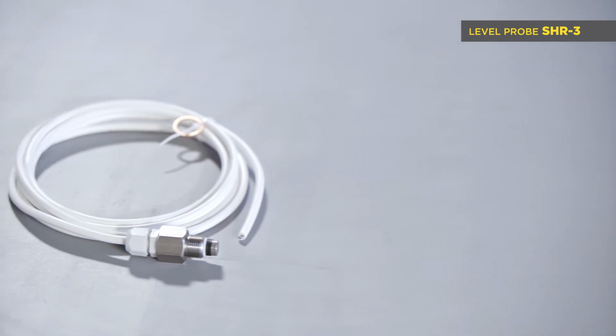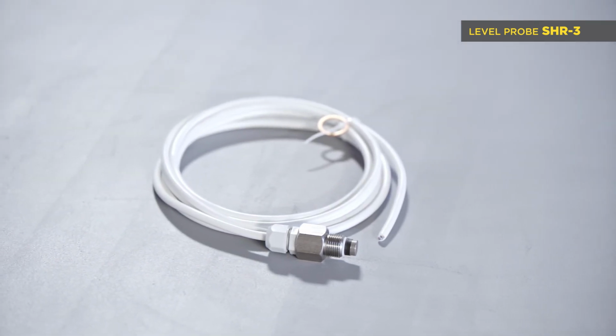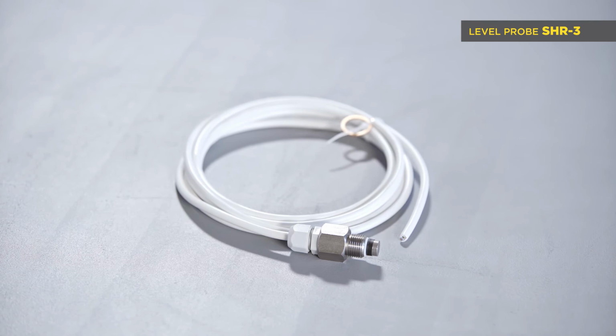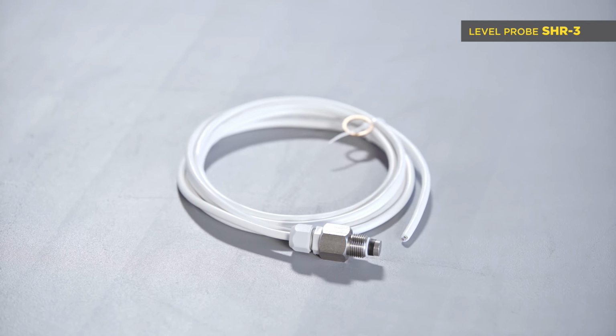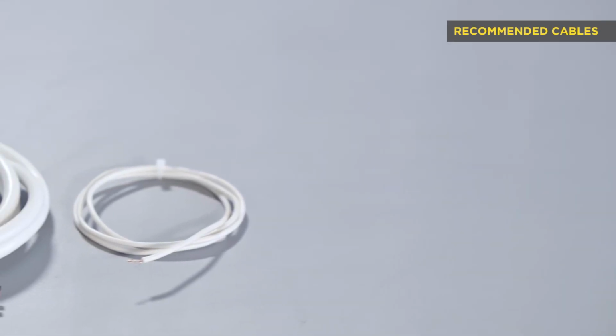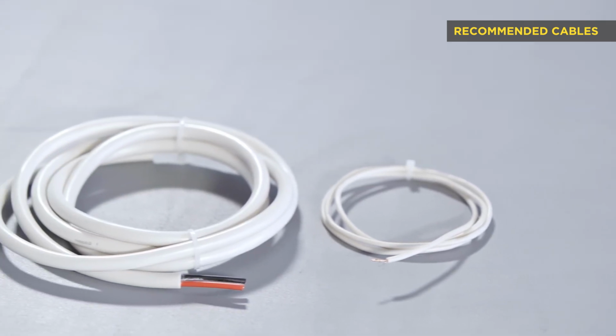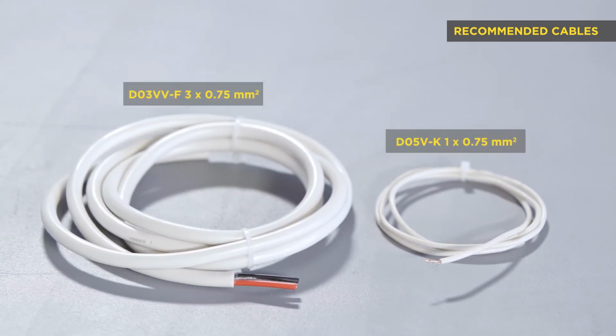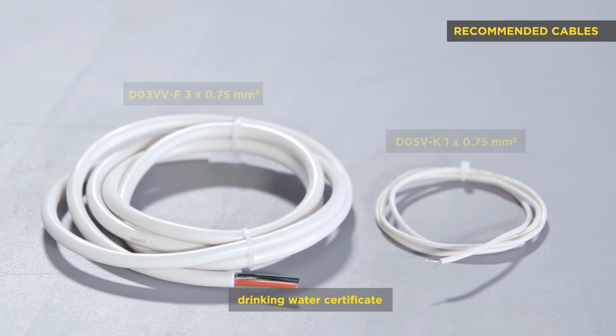SHR3 is an industrial electrode made from stainless steel with screw thread M18 with 3-meter long cable. It is suitable for direct installation into a closed tank with pressure up to 4 megapascal and operating temperature from minus 25 to 60 degrees Celsius. We also offer another accessory, a probe wire with 1 by 0.75 millimeters squared conductor, or a cable with 3 by 0.75 millimeters squared conductors with certification for drinking water.